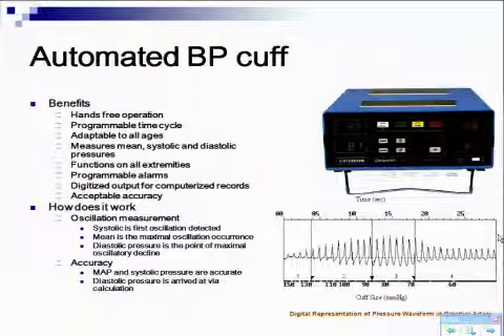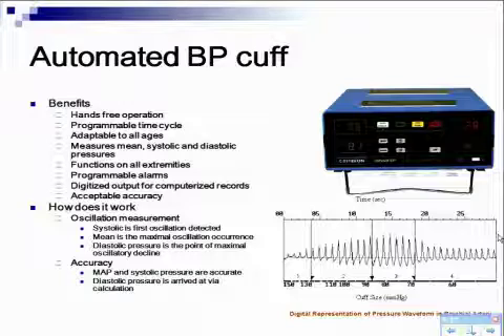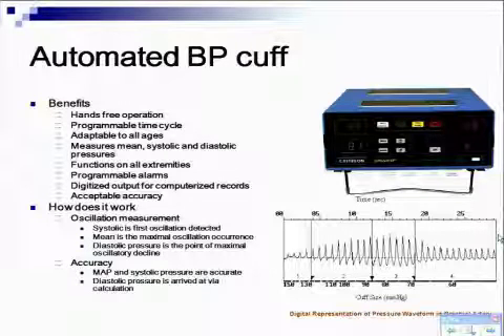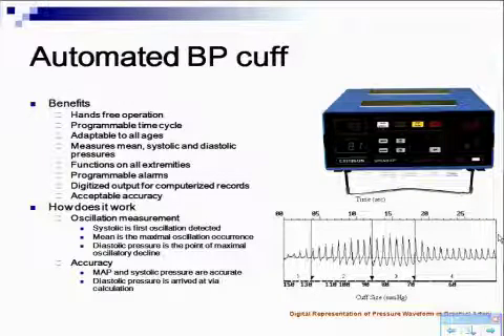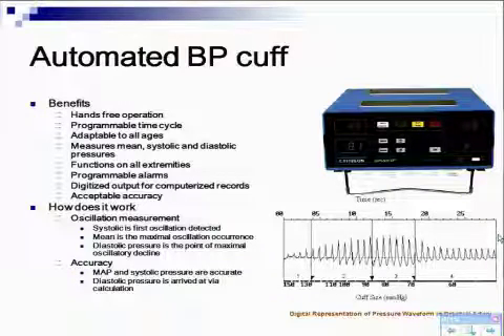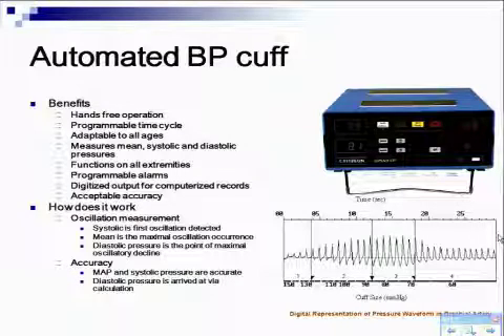So the initial Critikons are actually extremely accurate at systolic and mean arterial pressure. And when correlated to Korotkoff sounds, which is a non-invasive, non-automated measurement, it was very accurate. But the only measurements we got when we first got the first machine were systolic and mean. There was no diastolic measurement. And most of us said, you can't sell us this. Nobody's going to buy it. If you don't have a diastolic pressure, then I can't put it on my paper, and then it looks bad. It looks like I'm not monitoring.